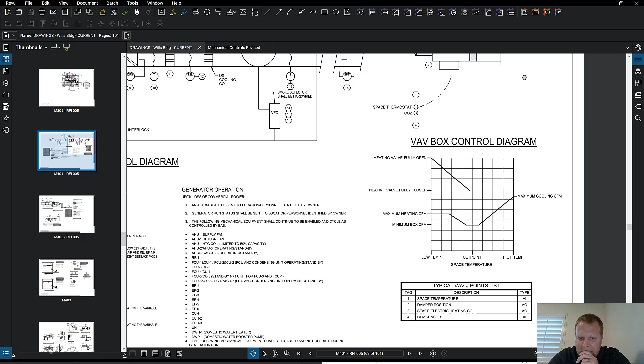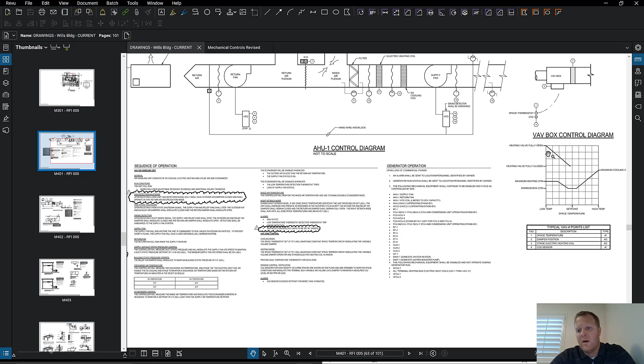So I should say VAV with a heating terminal, I think, is the more correct way to say this, because the VAV just adjusts the damper, right? And then the terminal can heat up the air again, because the air is coming out of this at, I forget the temperature range, but 65 and 55. So it's coming out at either 65 or 55 based off the return air temperature. Then it hits this VAV box, and one option is for the box to open and close the damper a little bit to let more air in based off whether it needs more cooling or not. And if it needs more air for the air exchange, but the air is too cold, it turns on the terminal here, and the terminal heats up the air so that it's not cooling the space too much while it's trying to provide the air exchange, right? Okay. We talked a lot about this.